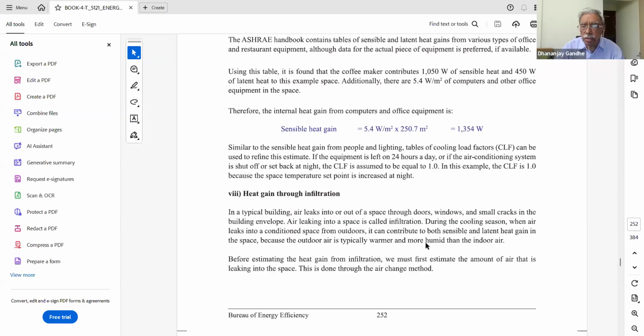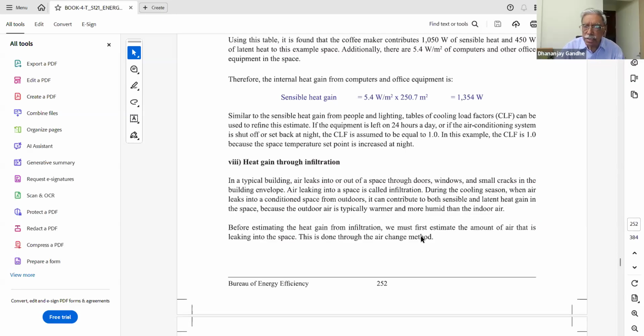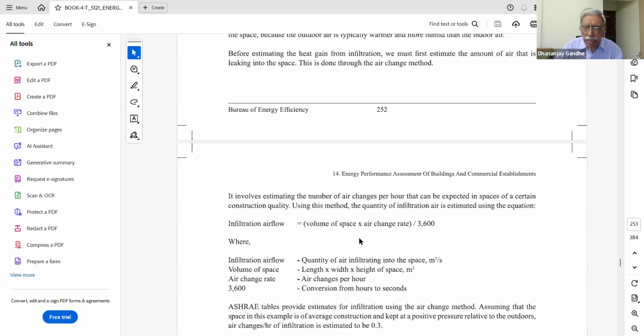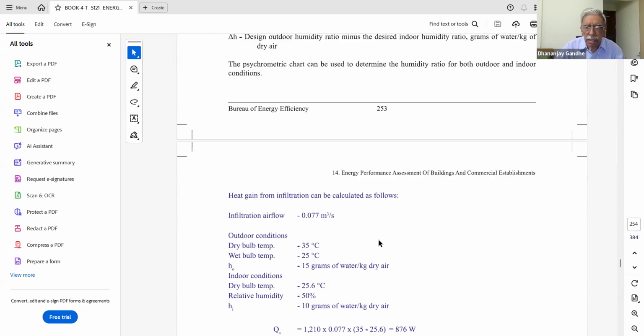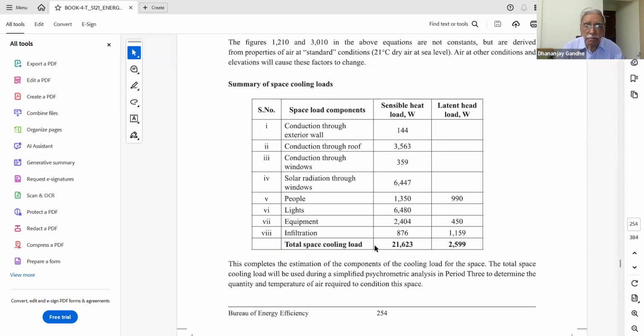So also the air that comes in gets infiltrated through the leakages, through cavities in the wall, doors, or maybe windows. So that is also calculated. Formulae are given over here, so you can calculate the heat gain from the infiltration air. So again, the summary table is mentioned over here, whereas in the earlier one we had mentioned these figures in the summary table: conduction through exterior walls, conduction through the exterior roof, conduction through windows, radiation gain through windows, and the conduction. So these two are different. Radiation is what directly passes, solar rays pass inside. Conduction is because the temperature outside is higher than the inside, so there is a conduction of heat. So these two components are different. One is the solar radiation passing through the window glass, and one is the conduction from outside air to the inside air because of the temperature difference.